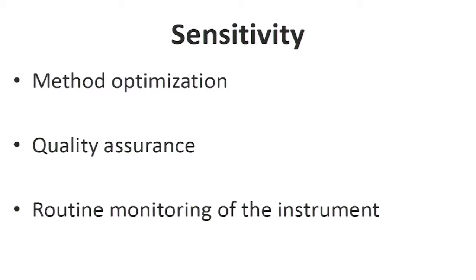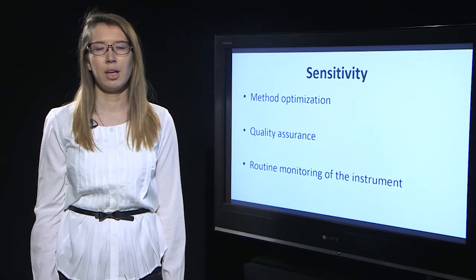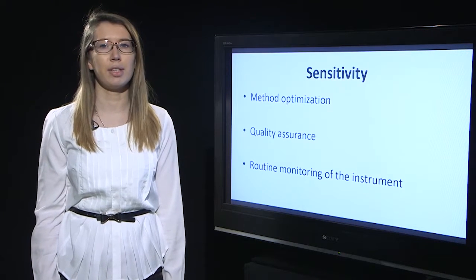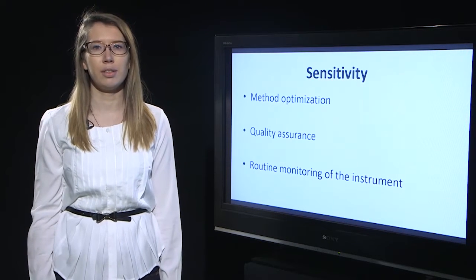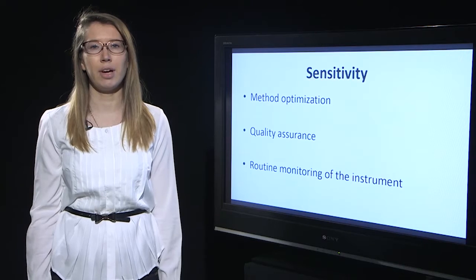Sensitivity can be useful during method optimization, where it can give us feedback about the changes made in the method. It can also be used in quality assurance procedures or just routine monitoring of instrument performance. Continuous monitoring of sensitivity can be especially useful for LC-MS analysis, where the sensitivity can vary between days.